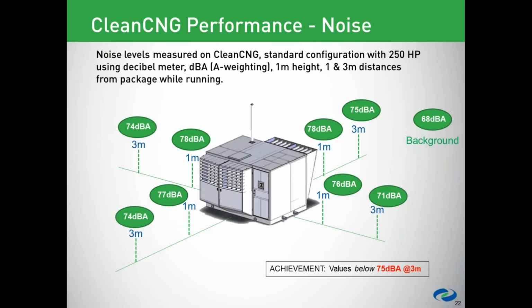If you take an air-cooled heat exchanger and drop it on top of a water-cooled system and then start taking measurements, your noise levels will change substantially. The key thing to remember here is you are looking at a completely integrated package with all cooling and all the components required on this footprint and within this envelope by these noise measurements.